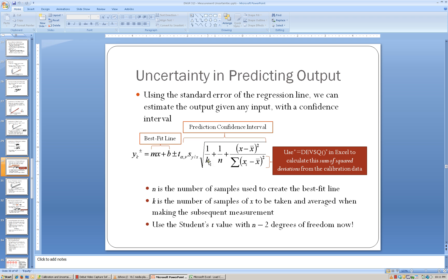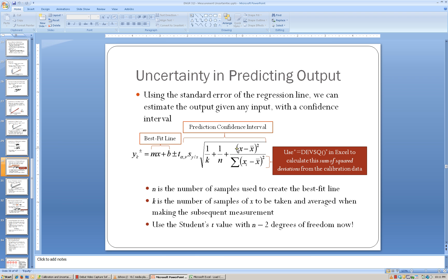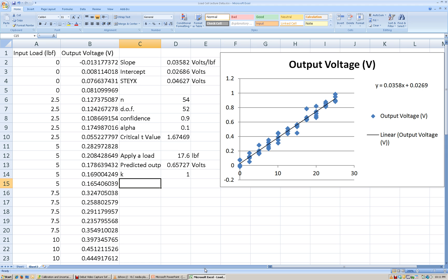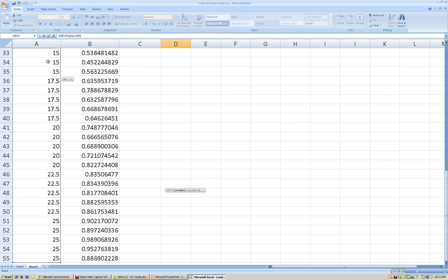We need to know how many samples we're going to use, so we'll take k to be 1. Our N — the number of samples used to create the calibration line — is 54. The denominator of this fraction can be calculated using the DEVSQ function in Excel to find the sum of squared deviations from all of the X values, all of the input loads. I'm going to take all of the X values — all of the input values — and calculate those.